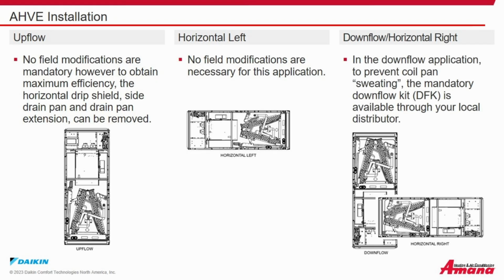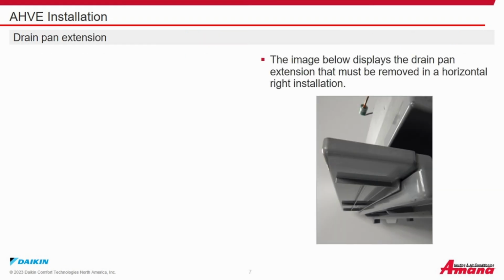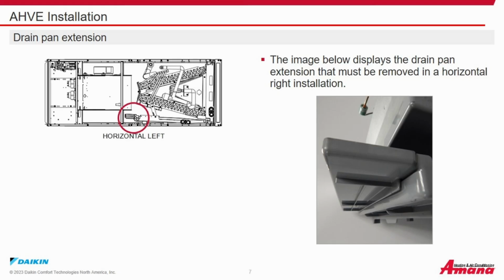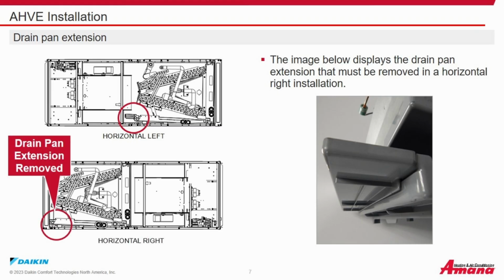For downflow and horizontal right orientation, in the downflow application, to prevent coil pan condensation or sweating, the mandatory downflow kit, DFK, is available through your local distributor. Drain pan extension. The image below shows the drain pan extension that must be removed in a horizontal right application. This diagram shows the drain pan extension installed in a horizontal left application, but it must be removed in a horizontal right application due to coil positioning.